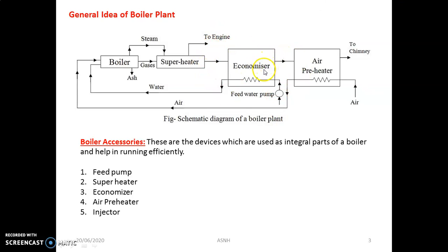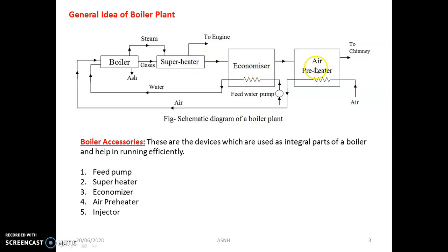The second accessory is the economizer. The main function of the economizer is to supply heated water to the boiler, and this is done with the help of flue gases. The flue gases are continuously passed over the superheater, economizer, and air preheater. Keep in mind that no separate electricity is required for these three components. The economizer utilizes heat from the flue gases, converts the regular water coming from the condenser into hot water, and supplies it to the boiler in order to save fuel.